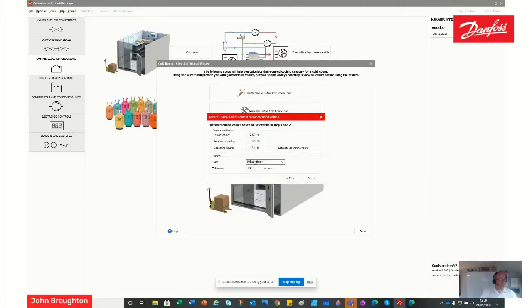Then we look at the type of panel. Again, this is automatically done in Coolselector, 100 mil. If your panels are thinner or thicker, then we can alter those parameters to suit. Obviously, thinner panels mean we've got more heat load coming in from the outside through the structure of the cold room. Thicker panels means we have less heat conductivity from outside to inside, so less heat load. So let's leave that as the default values.